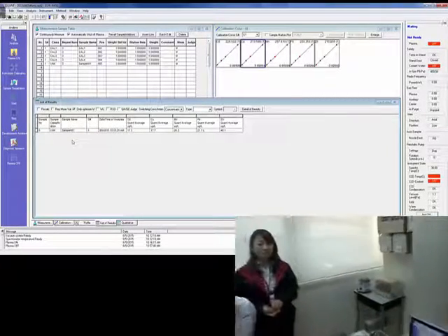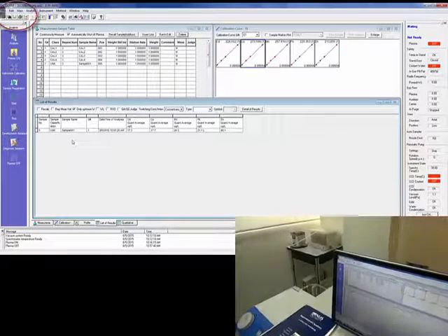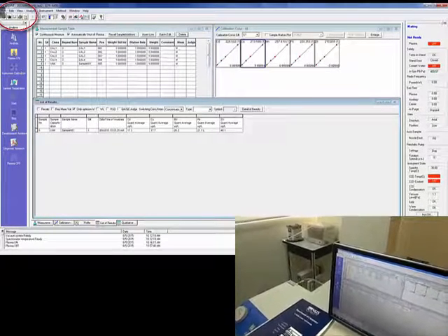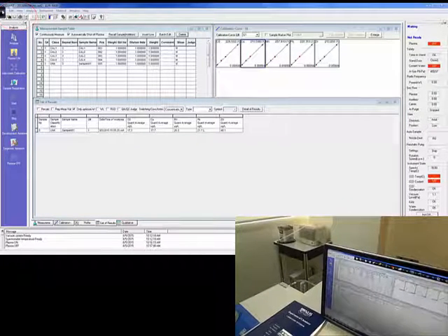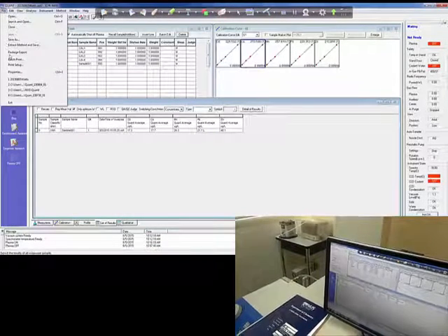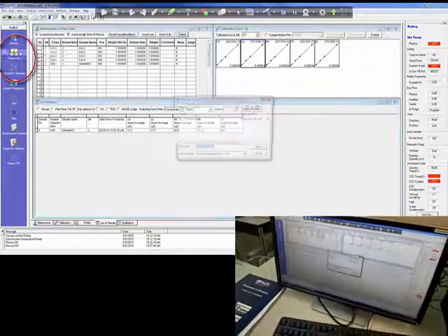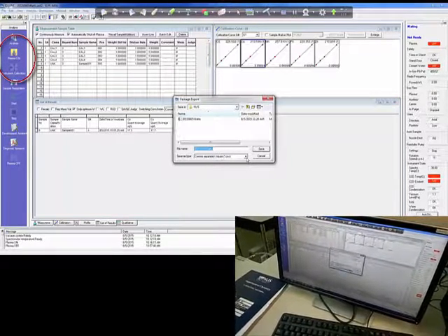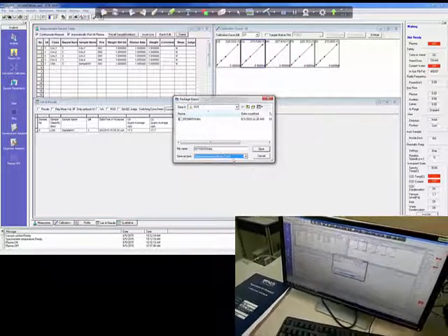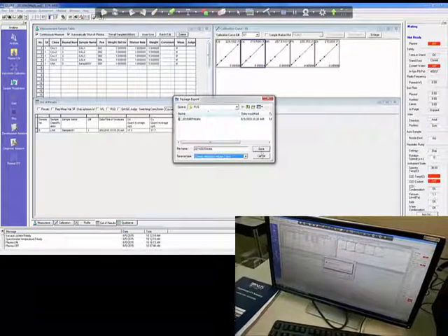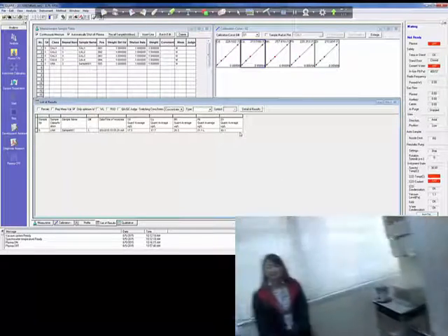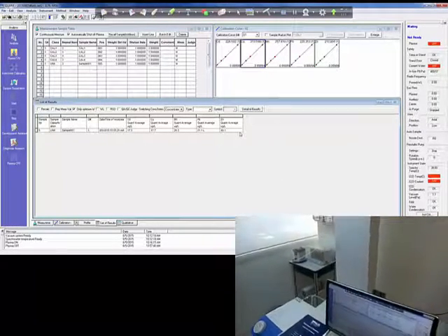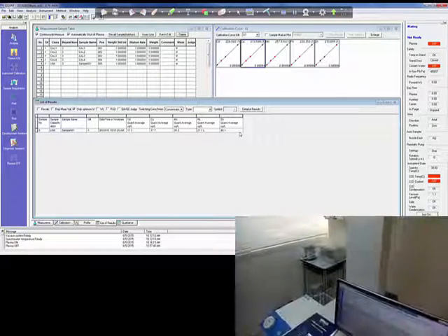If you then click File and click Package Export, and then choose—there are a number of options here—choose comma separated, CSV. It'll stick with the same name and save that as well. It will save that in the same location, and then there'll be two files there, which means for your logbooks, you can take that CSV file and read it using Excel.